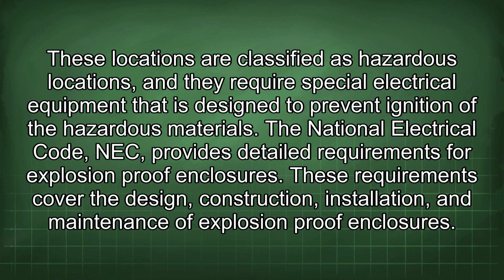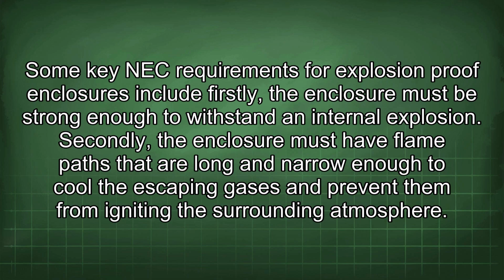the hazardous materials. The National Electrical Code (NEC) provides detailed requirements for explosion-proof enclosures. These requirements cover the design, construction, installation, and maintenance of explosion-proof enclosures. Some key NEC requirements for explosion-proof enclosures include: firstly, the enclosure must be strong enough to withstand an internal explosion. Secondly, the enclosure must have flame paths that are long and narrow enough to cool the escaping gases and prevent them from igniting the surrounding atmosphere.